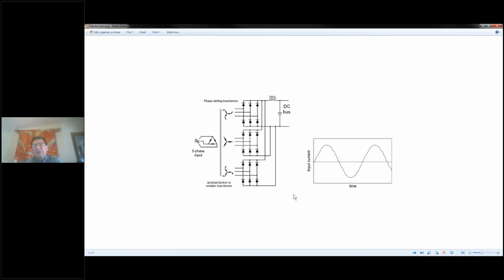When you have a failure in a drive, for example, a failed diode, Yaskawa's procedures say you should replace the entire diode bridge. Often that's not done for reasons of economy. But even if you replace the failed diode bridge entirely, that diode failing after 20 years is giving you an indication that some of the other components in the drive are also reaching the end of their service life. The capacitors, the transistors on the output, the diodes on the output, several other power components, not to mention the circuit boards themselves. So you've really got to consider that in terms of the customer's best interest by evaluating it on something other than just a short-term cost.